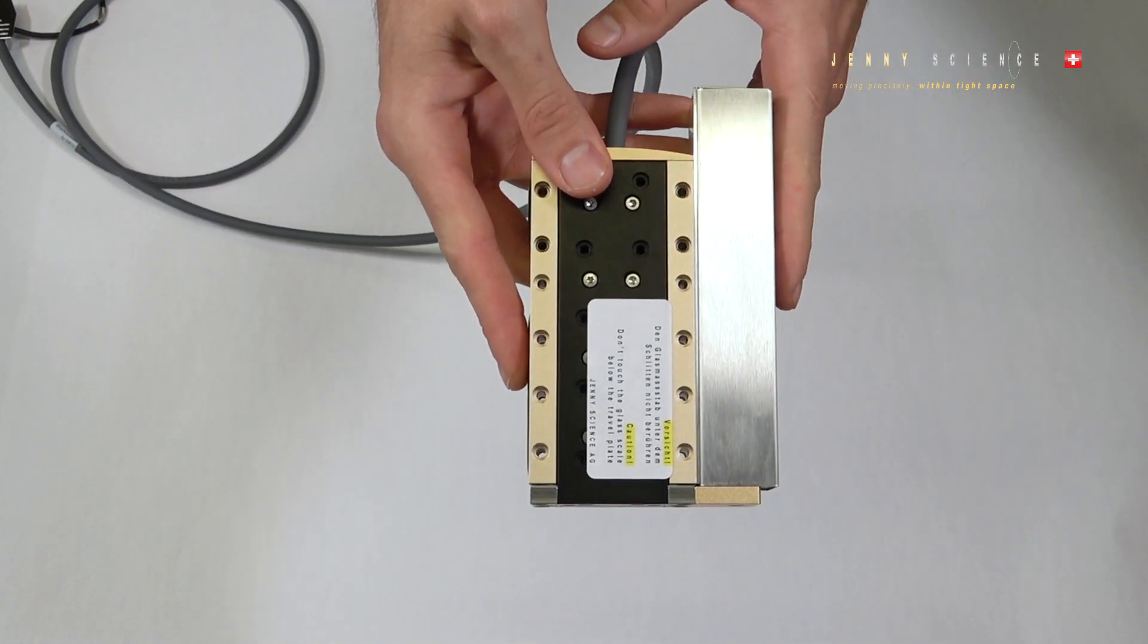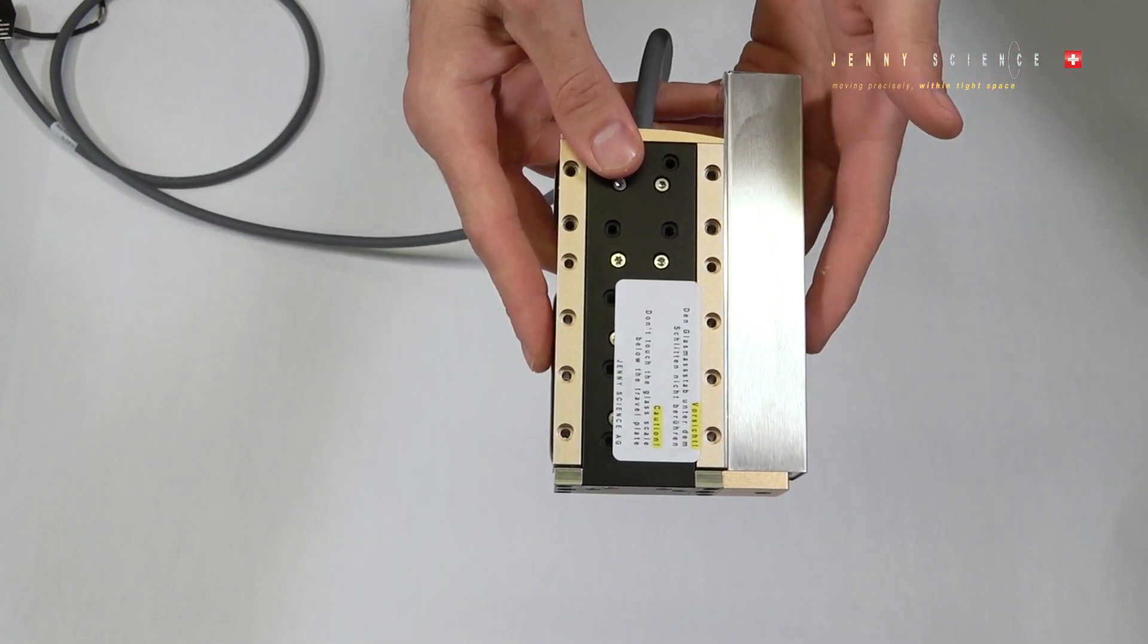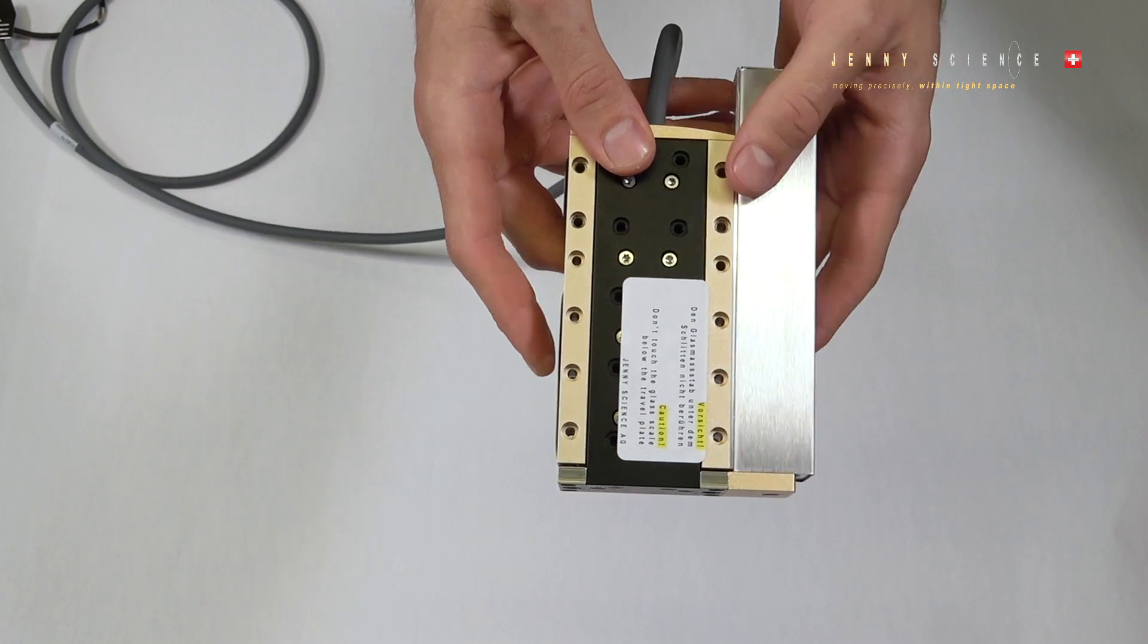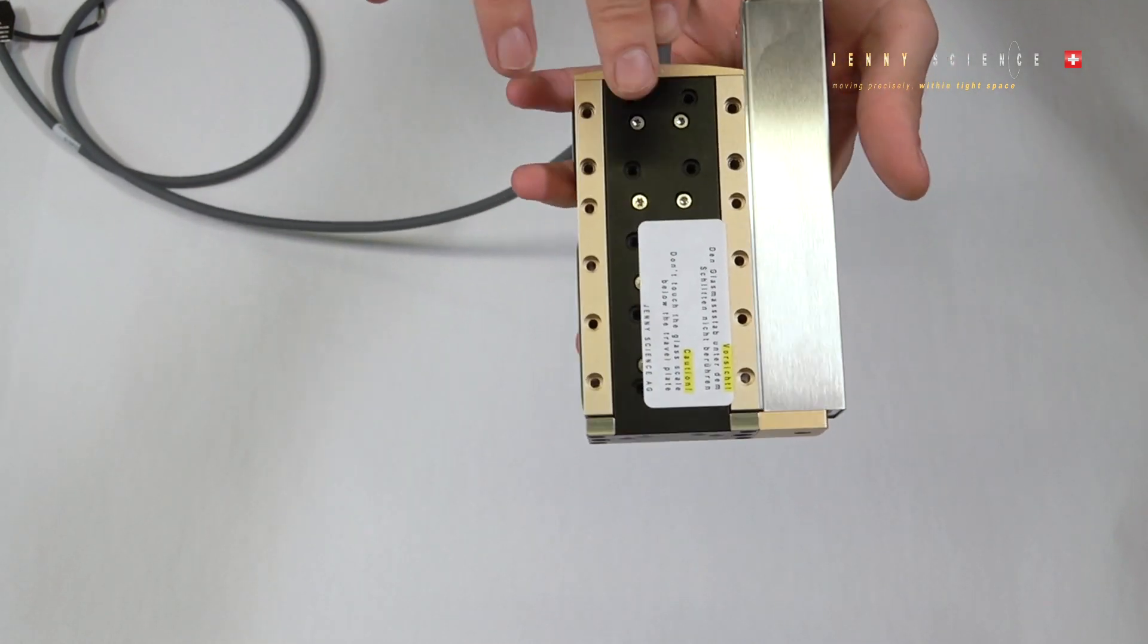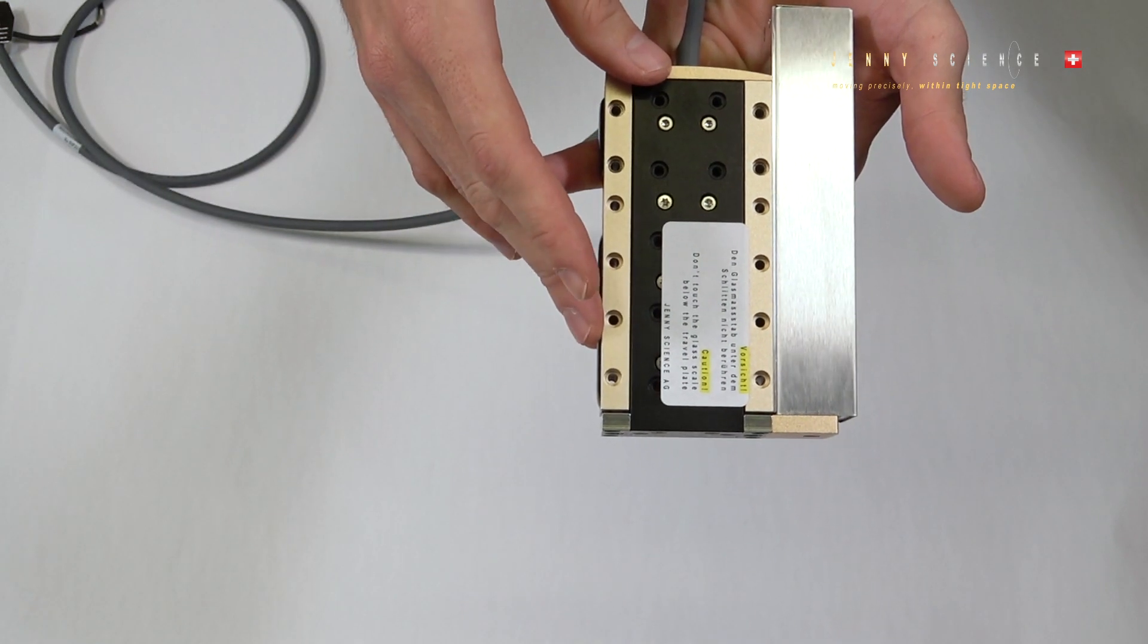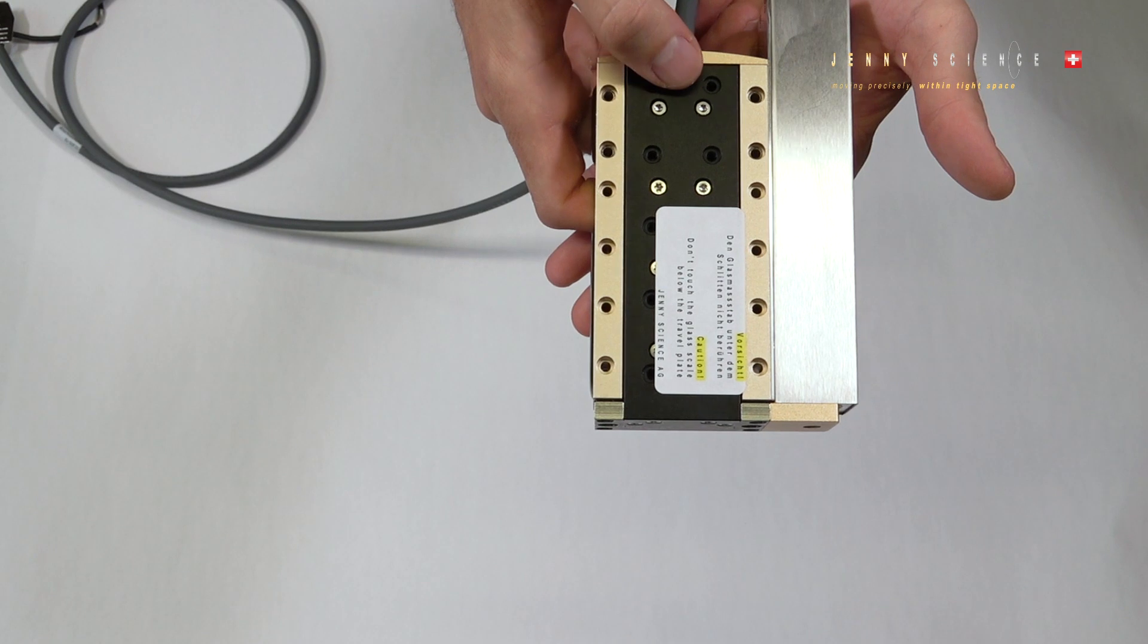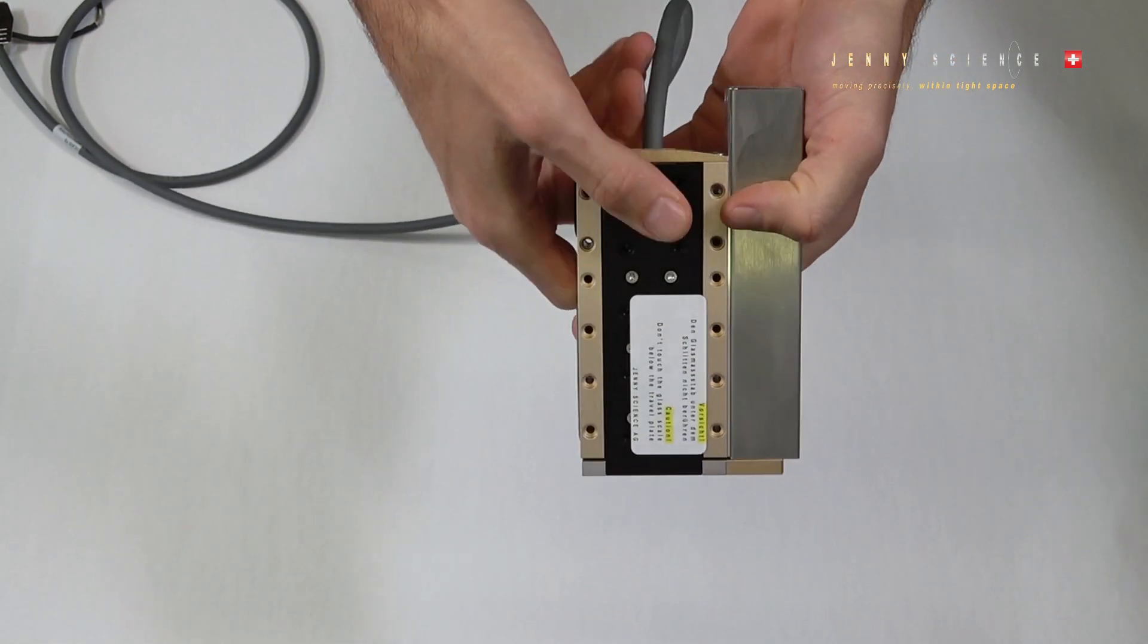Here on the left side we see the weight compensation which is important if you are using the axis vertically. It has two tasks. First of all it compensates the weight so the motor won't use its whole power for the weight and also if the power supply shuts off the motor won't fall down, it will go back up.